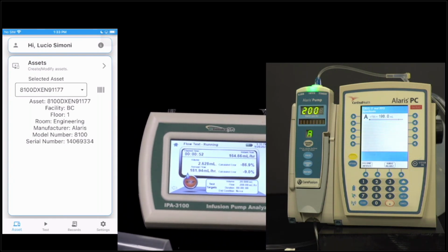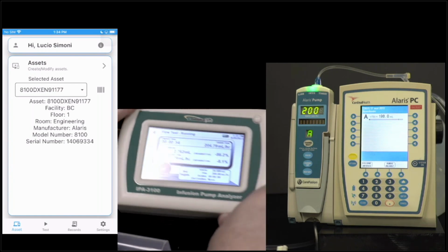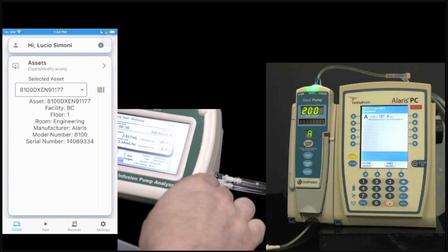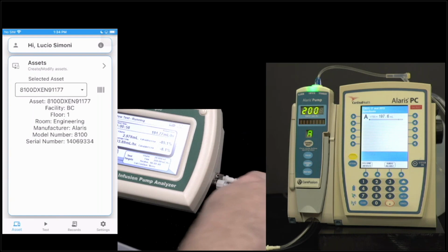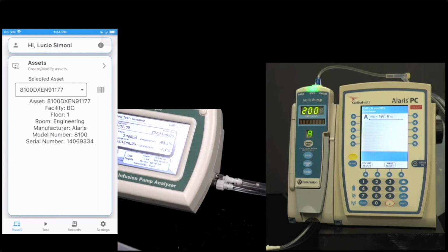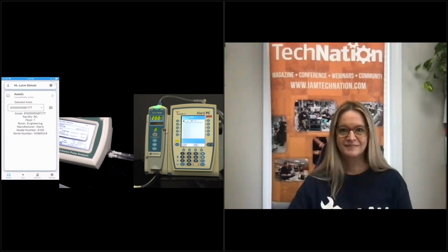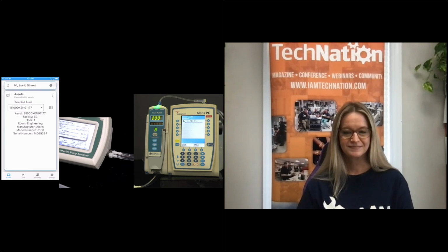Now we can see there's no alarm. There's no problem. We should actually see that air bubble working its way out of the drain tubing in a second. Everything continues to run, no problem. And that's based on the technology inside the 3100. It's not looking for an edge of fluid. It's not looking for bubble tracking. So bubbles really have no effect.